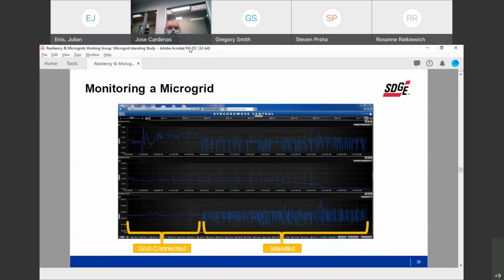So here we have our screenshot of our island transition. To the left, you have grid connected steady state. At the bottom, you have your frequency, then you have your current, then you have your voltage at the top. I'm going to focus here on the frequency, where this is super zoomed in. Pre-island, when you're grid connected, the frequency is really steady. You have the whole grid stabilizing the frequency. As soon as you go into this island transition, you're going to see the frequency oscillate back and forth. This is a characteristic of our generators. They have an envelope that they operate between.